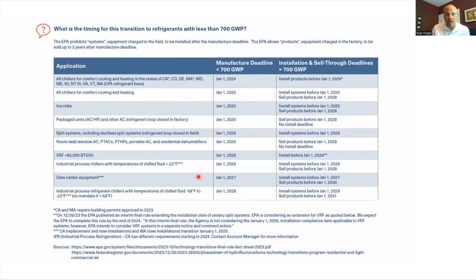VRF, that's above 5 tons, is similar to other split systems, but it has a bonus year. So they can be manufactured with 410A this year still, but it cuts off at the end of this year, and they can be installed next year, 2026, all the way till December 31st, 2026. They get an extra year because VRF is more challenging because you have a larger quantity of refrigerant. We'll explain some of that in later discussions today. And then the rest of these things are more specialty equipment. You can see them on the slide if you need to.